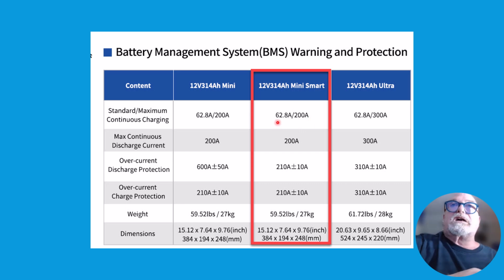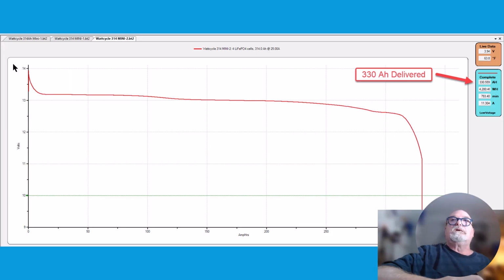So the recommended charge current is 0.2 C, or 20% of amp hour capacity, which on this battery is 62.8 amps. They've announced a new 314 amp hour Ultra, which is also 0.2 C. So even though it has a bigger BMS with a 300 amp discharge, the charge current is still 62.8 amps, which is 0.2 C. Maximum discharge is 210 amps plus or minus 10 amps. I found on my battery it's 210 amps plus or minus 5, but that's well within spec, and the spec's pretty accurate. Let's take a look at what I got from this battery when I discharged it. Again, this is the West Mountain Radio CBA 5 Pro, and it delivered 330.5 amp hours.